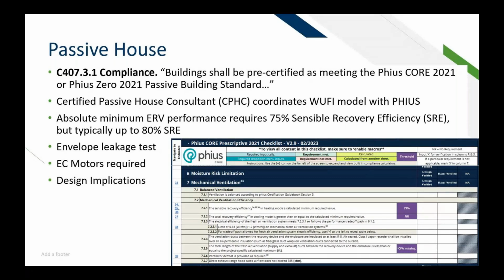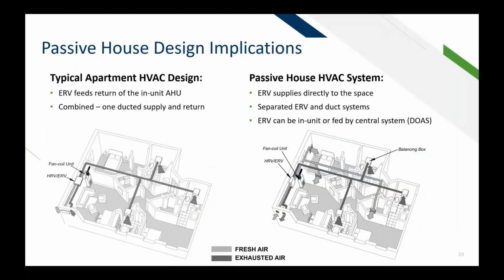So the envelope leakage test is also a big thing, and we'll talk about that in a second, but EC motors are going to be required. And then there's also some design implications. One of the big design implications that I've seen across the board is that the typical apartment HVAC design has kind of changed. Historically, your ERV has always fed the return of an in-unit air handling unit. That means the systems are combined. You have one ducted supply and one return, and you kind of tie your ERV efficiency in with the efficiency of the unit. However, passive house doesn't really like that. They actually want to see your duct systems completely separated. The ERV has to supply directly to the space because they want to be able to measure that. Now, I know that some people question this, but one of my engineers has had a conversation with them directly, and this is a hard rule that has come out of that.